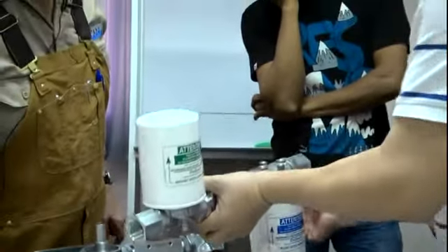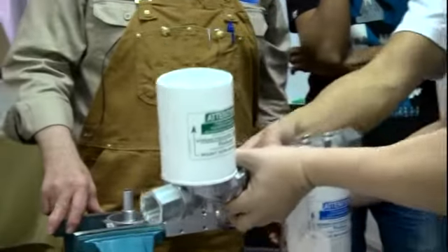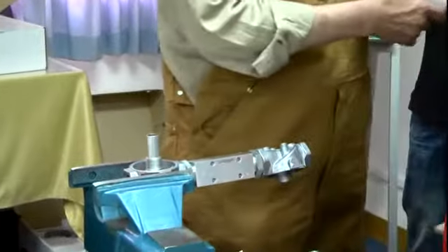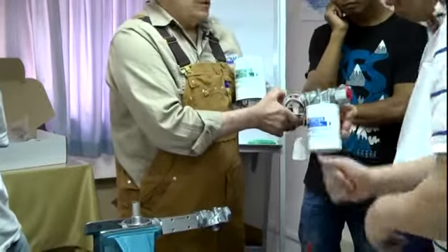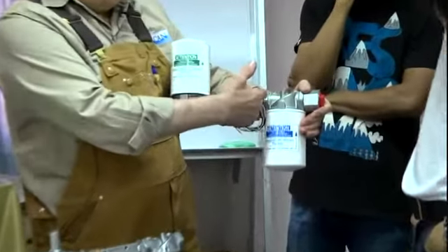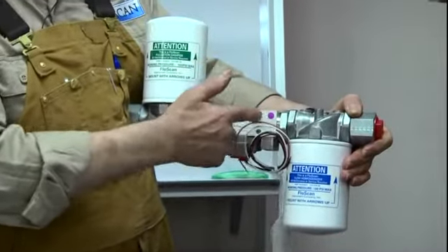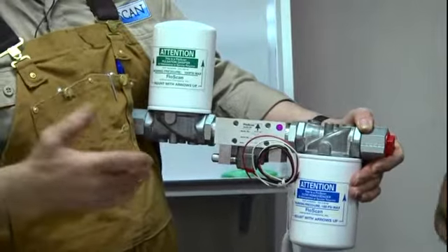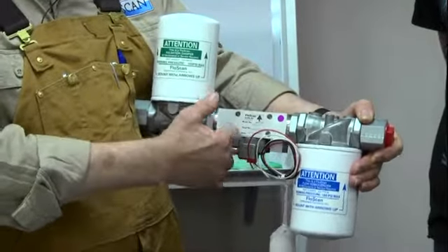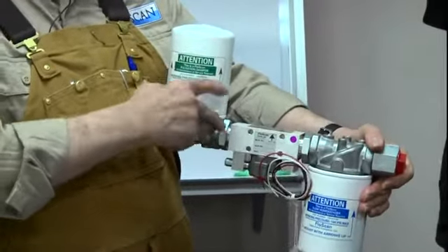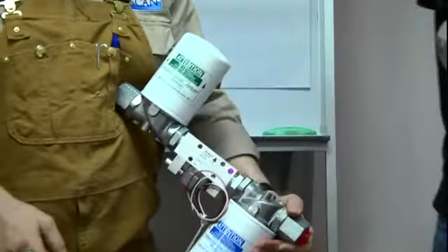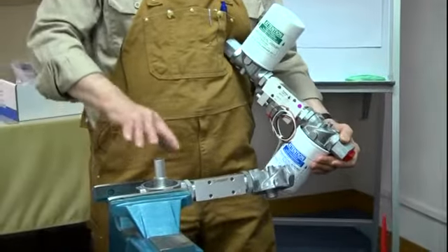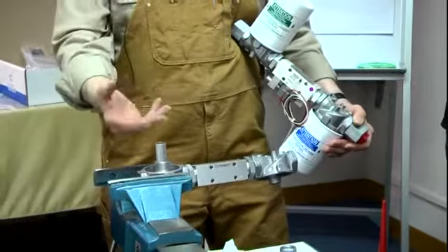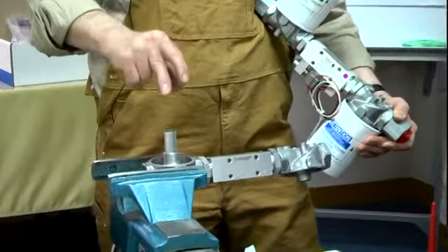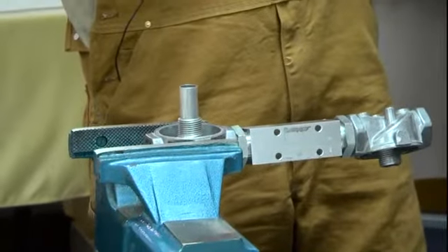Sorry, I don't understand this. When the oil flows in, it comes into here, goes through that canister, then comes into the block. Most of the oil goes through the block. A percentage of it, let's say 20%, I don't know what it is exactly, goes through the sensor, and then it joins back here, comes up, then it all goes up through the pulsation damper, comes into the body of the casting of the pulsation damper, fills up to the top of the standpipe, and then flows out. Hopefully we are pressurizing it a little bit, and we're trapping gases or vapors at the top of the damper.